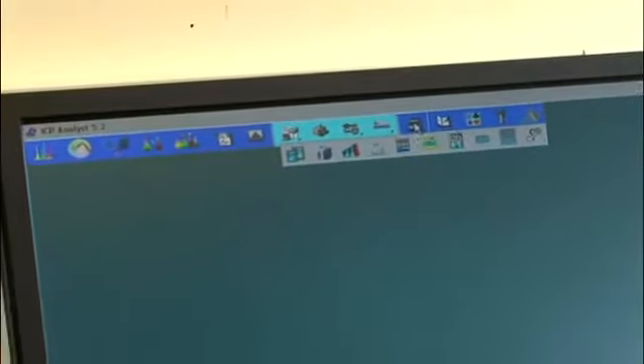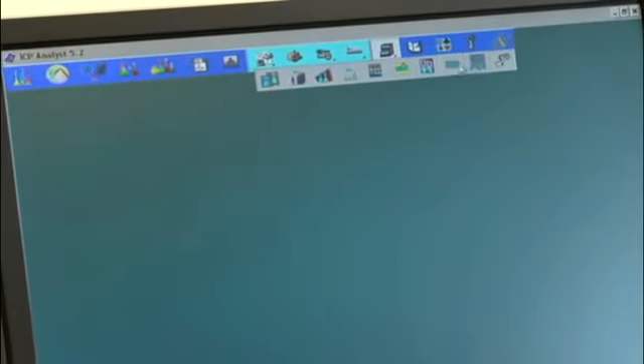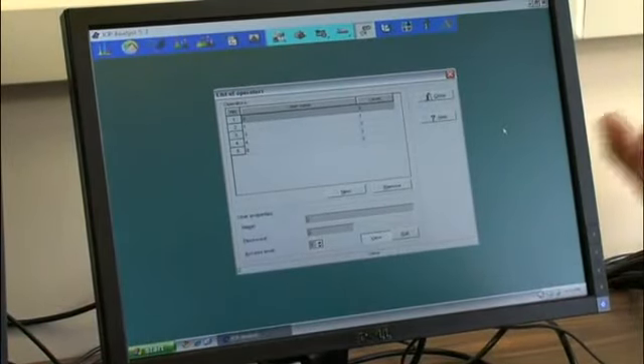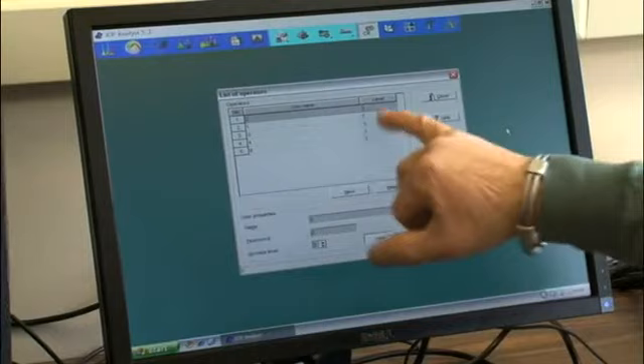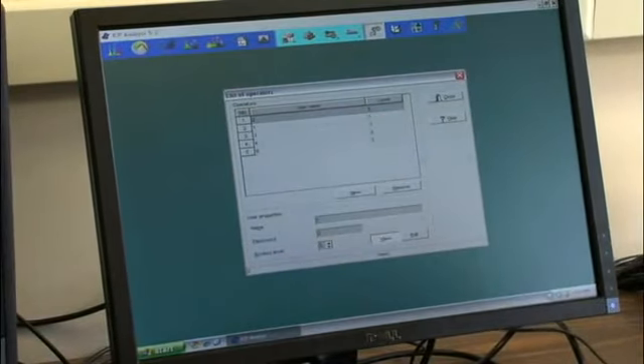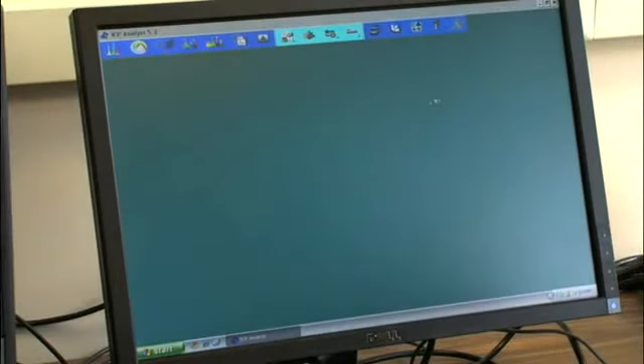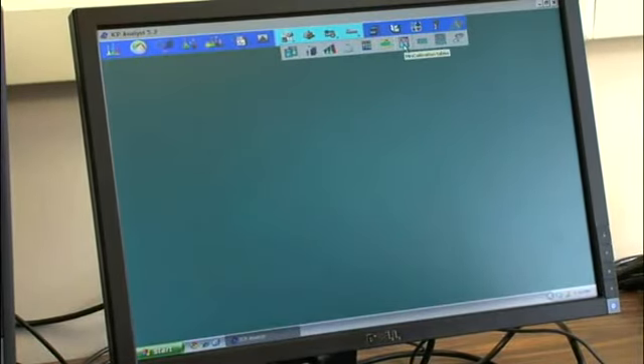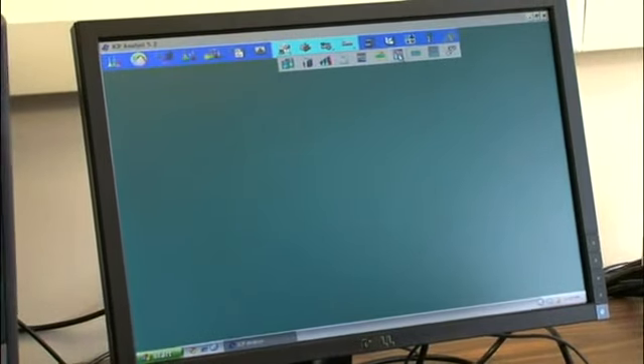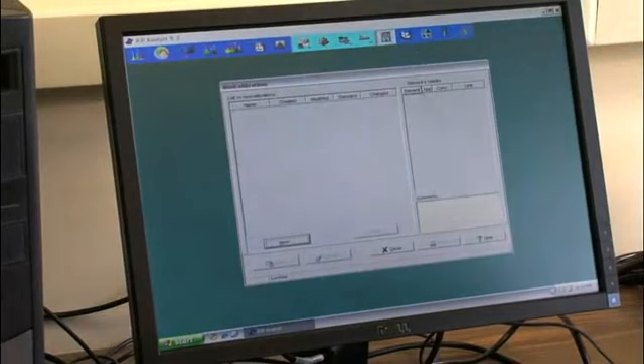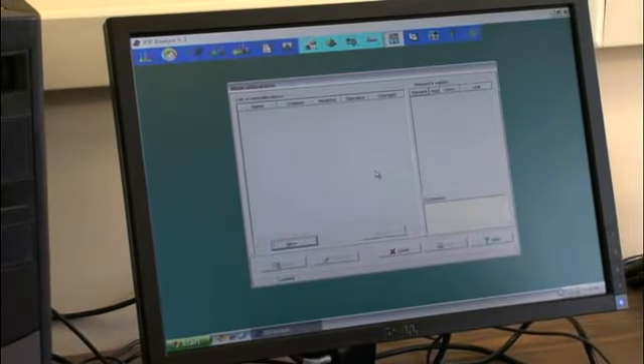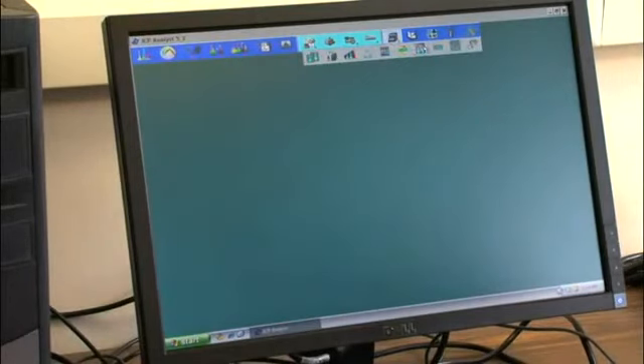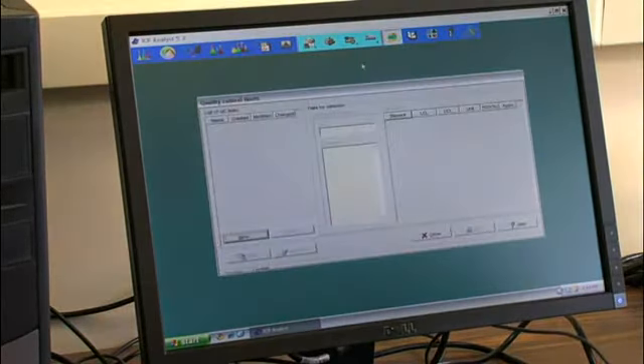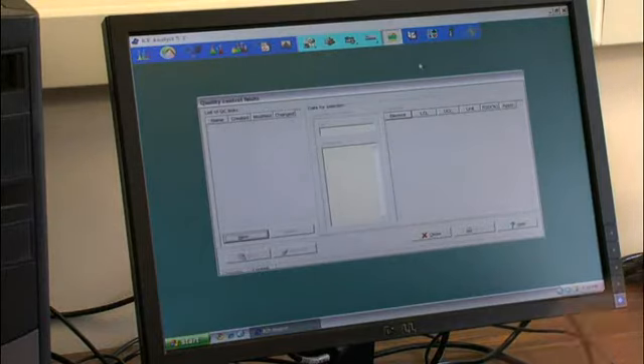Your management icon is for the databases of, well, you don't have an auto sampler, but these are auto sampler trays and racks. This is if you want to assign someone else permission to use this, but you don't want them to have access to changing a method, you can assign them a lower level. 3 allows you to do whatever you want. What else we got here? Some of these are kind of redundant, and I don't know what all of these are used for, but mini calibration, it's a database of a calibration table if you make one up. Control tables, that's for, I think that's used like for in-process controls.